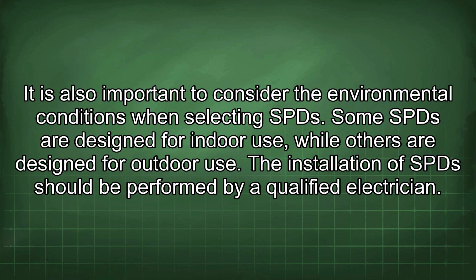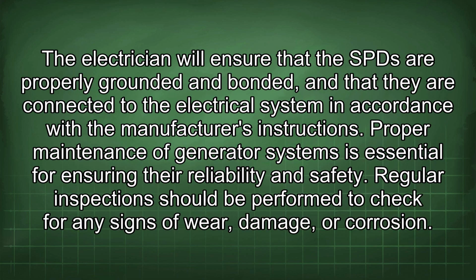Some SPDs are designed for indoor use, while others are designed for outdoor use. The installation of SPDs should be performed by a qualified electrician. The electrician will ensure that the SPDs are properly grounded and bonded, and that they are connected to the electrical system in accordance with the manufacturer's instructions.